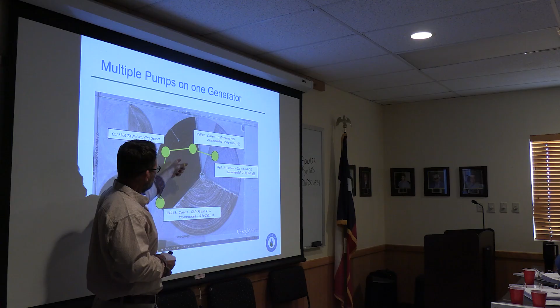Going back to this, you can see that there's a lot of lines. You've got to run a line here, a line here, and a line here. An example of a line loss calculation would be: what's your volts and amps at the gen set, all the way out to the volts and amps at the submersible. You see you've had a little bit of a voltage drop, which is going to happen. The amps are pretty consistent because amps really measure the work that's getting done here. But you can calculate the difference between the available energy at the start and the available energy at the location, and you can figure out what type of power you're losing.